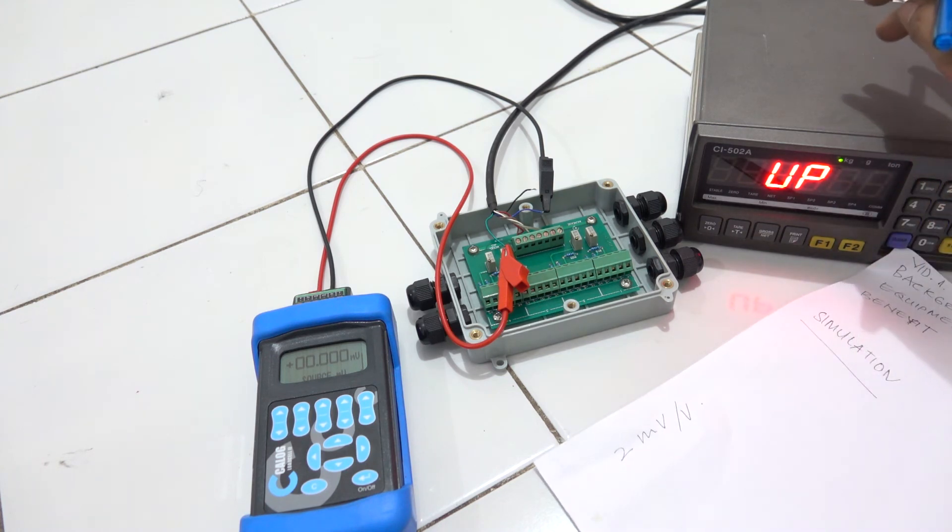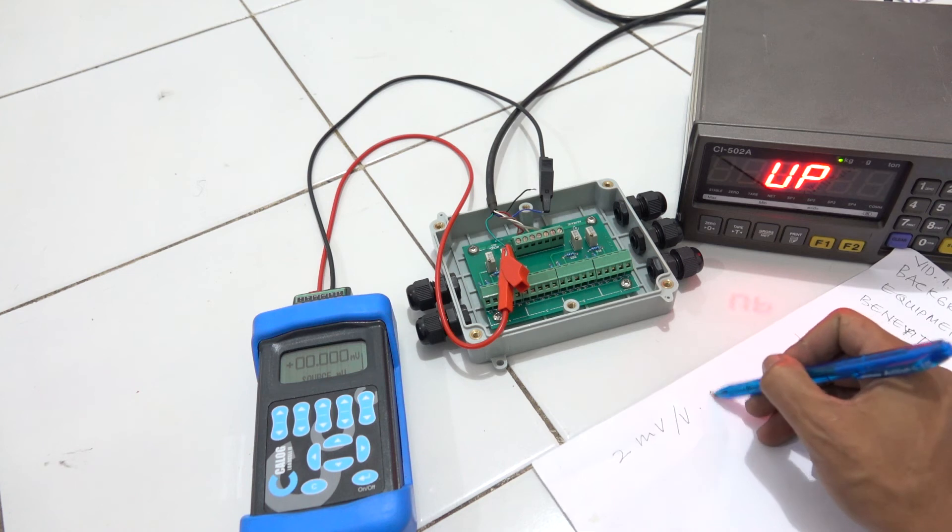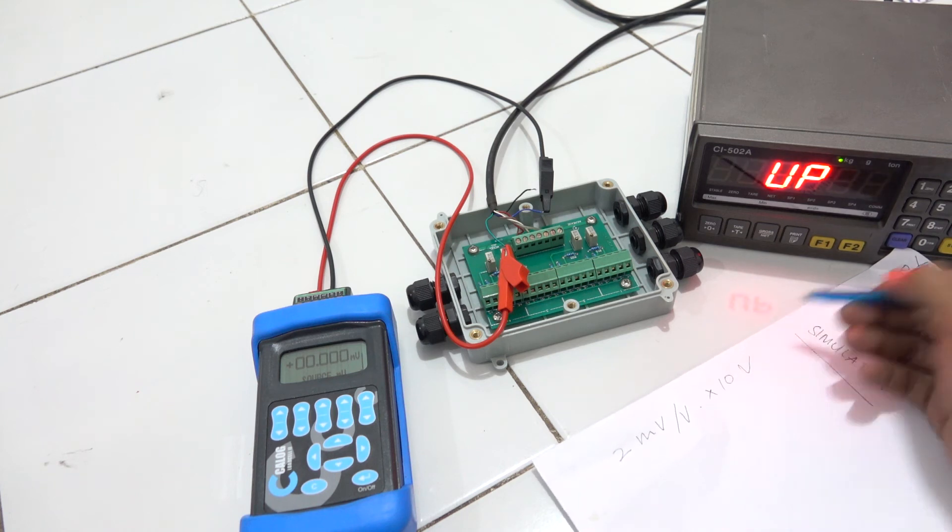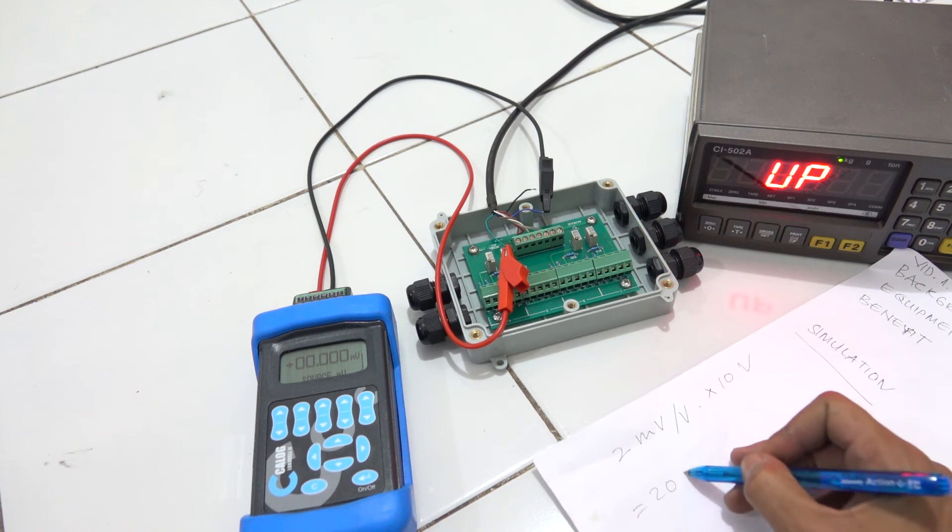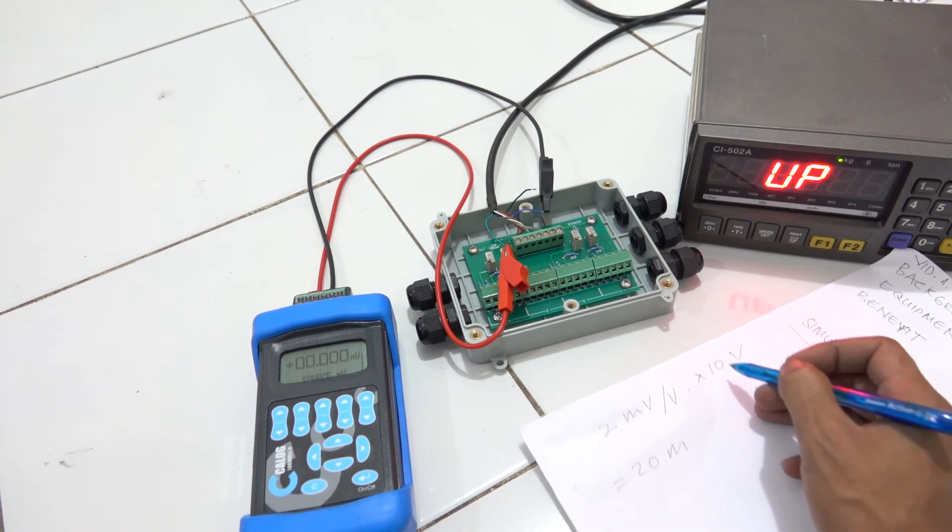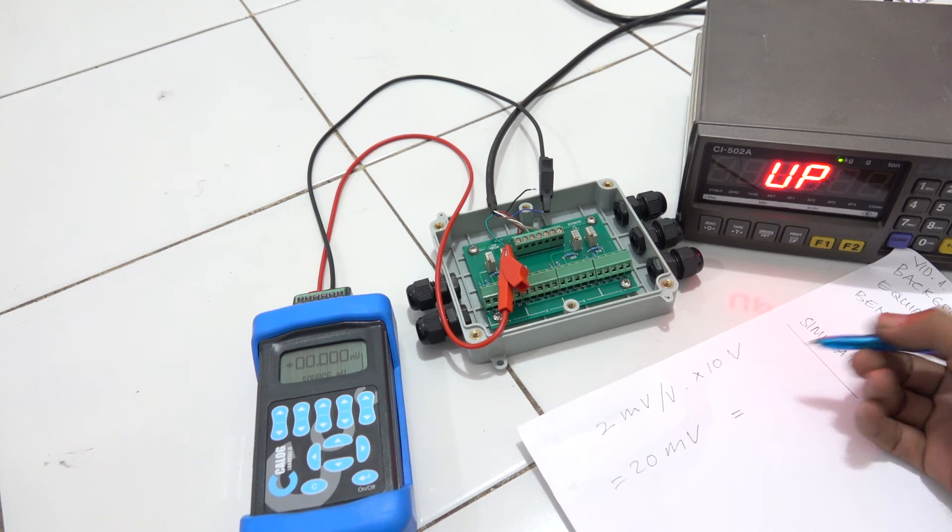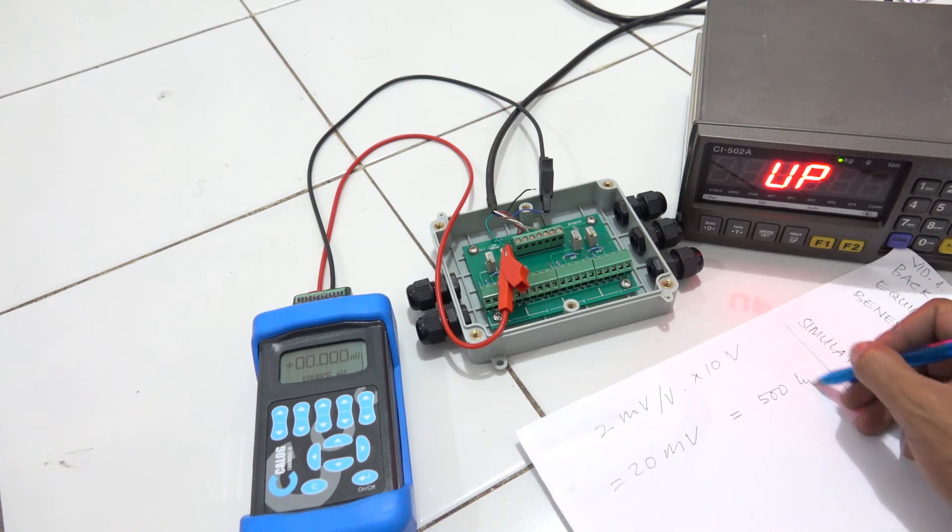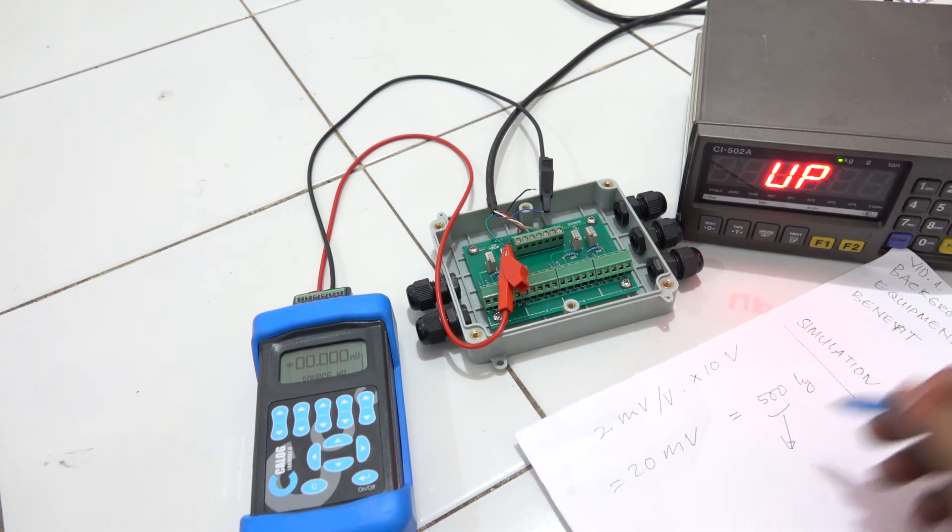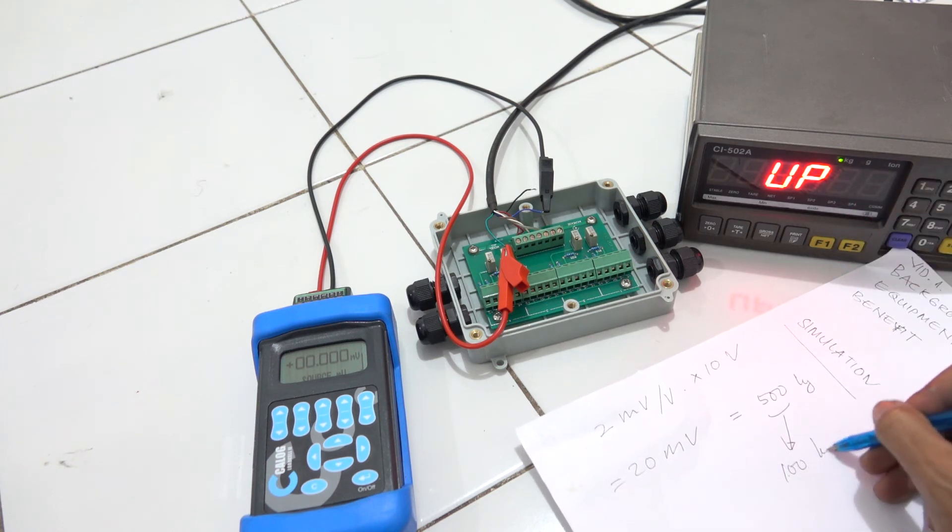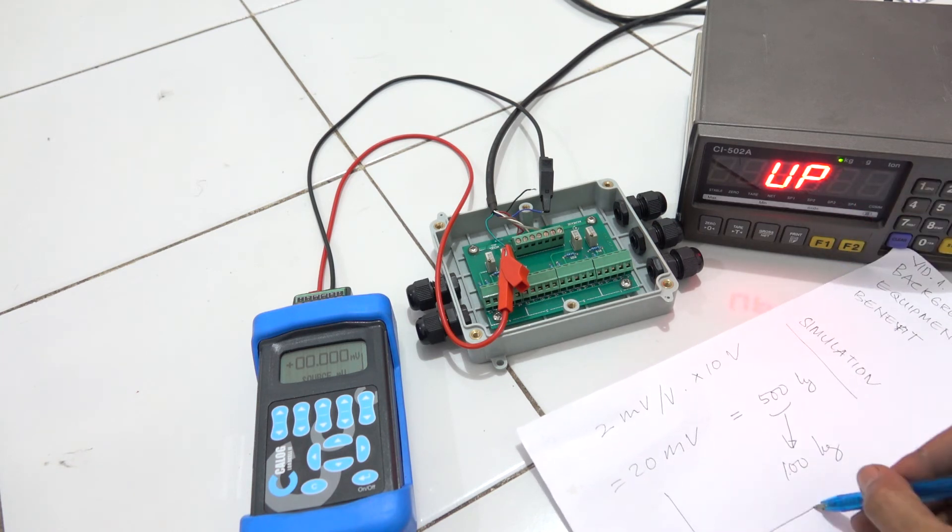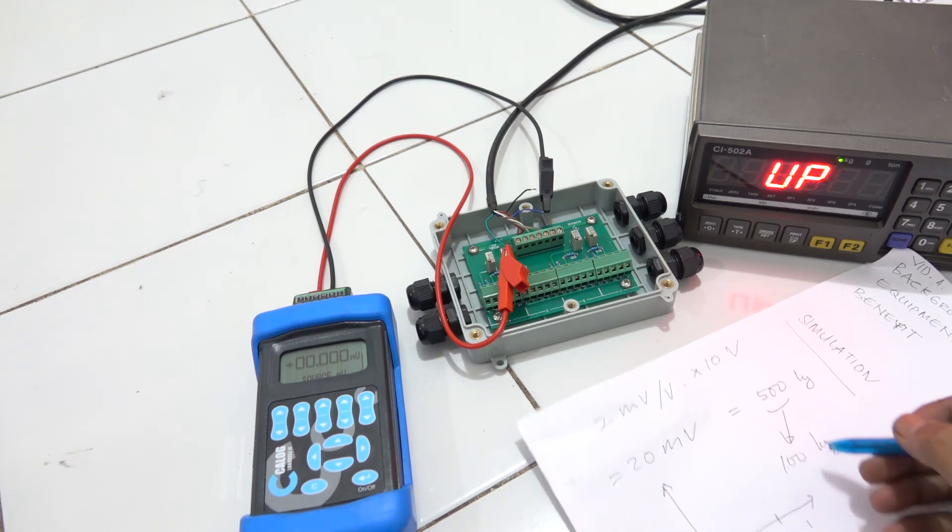I just multiply 10 volt, and then you have 20 millivolt that equals 500 kg. Previously you wanted to make a span calibration at 100 kg, so we just make it linear. It's 20 millivolt.